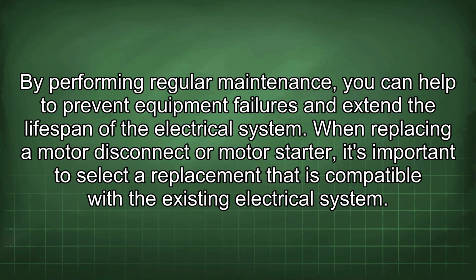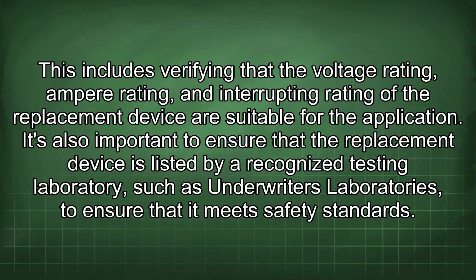When replacing a motor disconnect or motor starter, it's important to select a replacement that is compatible with the existing electrical system. This includes verifying that the voltage rating, ampere rating, and interrupting rating of the replacement device are suitable for the application. It's also important to ensure that the replacement device is listed by a recognized testing laboratory, such as Underwriters Laboratories, to ensure that it meets safety standards.